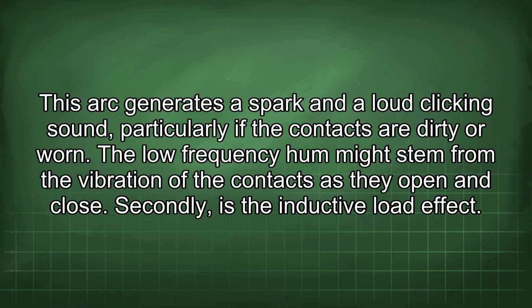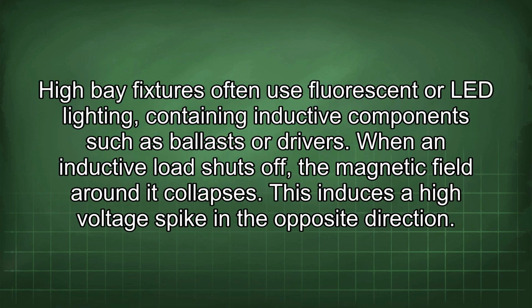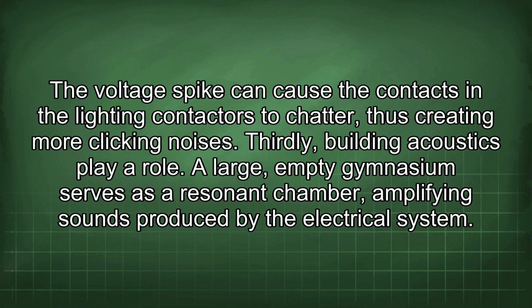Secondly is the inductive load effect. High bay fixtures often use fluorescent or LED lighting containing inductive components such as ballasts or drivers. When an inductive load shuts off, the magnetic field around it collapses. This induces a high voltage spike in the opposite direction. The voltage spike can cause the contacts in the lighting contactors to chatter, thus creating more clicking noises.